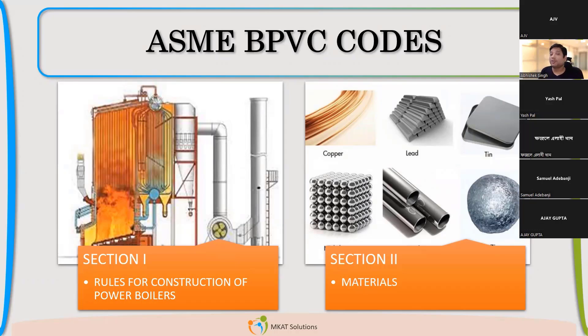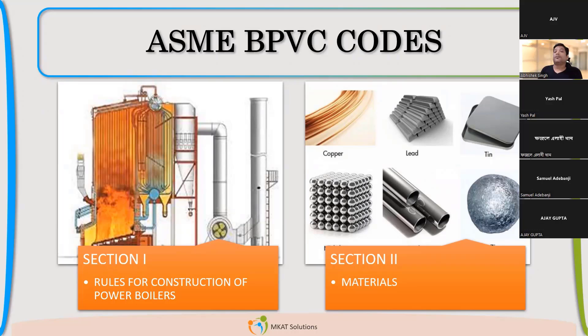Section 2 is similar — it caters to lots of different codes. There are different stress tables, so when referring to allowable stress from Section 2, you should be very careful which table you are referring to. For Section 8 Division 1, Table 1 applies; different sections have different tables. You have to pick the allowable stress accordingly, because the factor of safety is different and allowable stress directly reflects the factor of safety — there is no separate factor of safety mentioned in the code. Allowable stress takes care of your factor of safety.